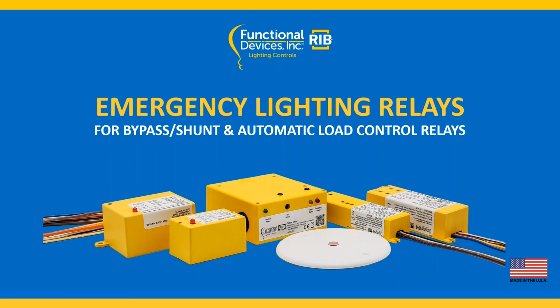In addition to the NEC code information that Matt shared, there are basically 3 types of emergency lighting controls. There is a bypass shunt, there are automatic load control relays, also known as ALCR, and the last is the automatic transfer switch, also known as ATS. Today, we're going to be looking at UL 924 bypass shunt and automatic load control relays.